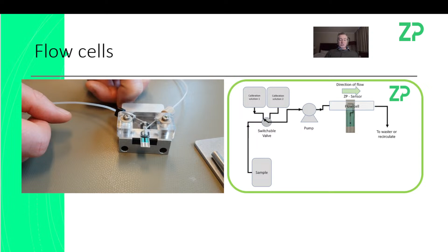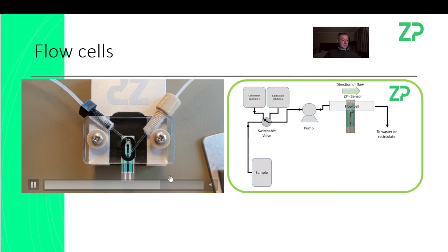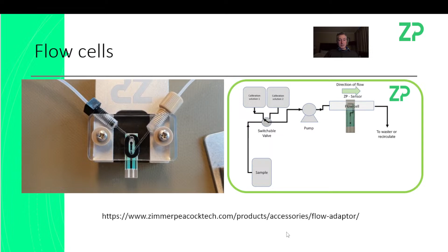I've said it before, but most of the sensors that we build, we try to build for continuous measurement. And because we build them for continuous measurement, that also gives the ability to be reused. That reuse works really well in this chemical analyzer space because you have the ability to do calibrations as well. So if there's any sort of damage or drift in the sensor, it can be calibrated essentially back out of the signal. And if you see a link, I've already put the link underneath the video, and I really hope that will help.